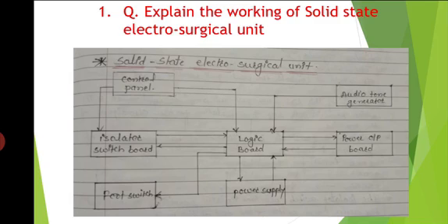A thermostat is sometimes mounted on the power amplifier heat sink. If the temperature is too high, it becomes open circuited, signaling an alarm and interrupting the output. The output circuit in a diathermy machine is generally isolated and carefully insulated from low frequency primary and secondary voltages.